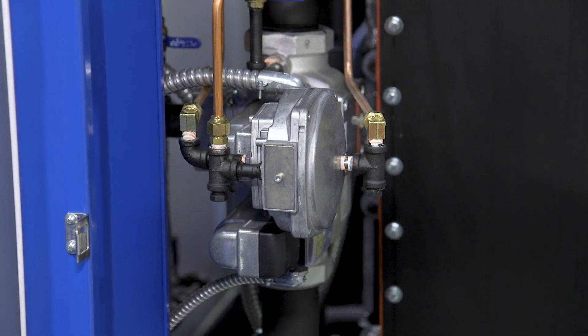The difference between this and traditional fire tubes is that our boilers are a single-pass steam generator. We can say boiler and steam generator interchangeably, but with our machine from cold steel to full steaming it's going to be about five minutes until it's ready. That allows us to stage these modularly and be an on-demand system such that you'll only have the steam that you need when you need it — no time or money wasted heating thousands of gallons of water when you only have a hundred gallons to worry about.